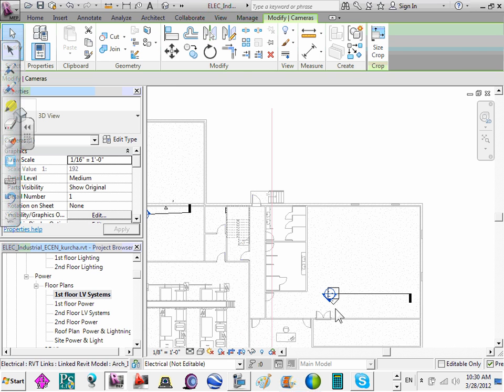Is this a mechanical? This one is the UPS area, UPS on the batteries. Right, so this might be where they're going to put their pre-action panel and start their dry pipe system from. They're going to have an air compressor in there, and you're just going to monitor the flow, tamper, and high and low air on that one system. Because if there's low air in the system, water's going to shoot through, and especially in data rooms, the worst thing for them is water.